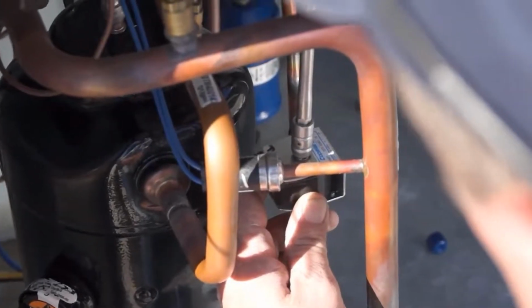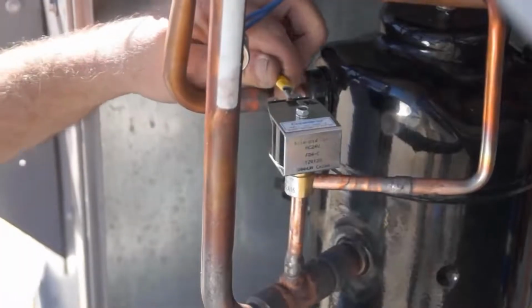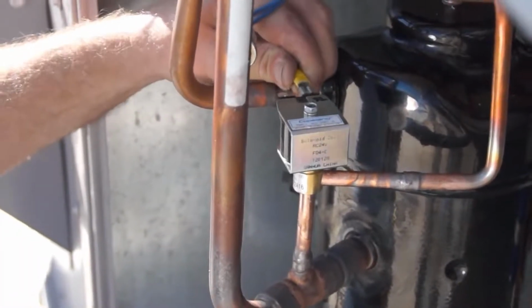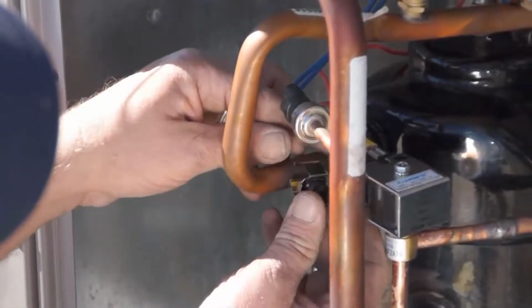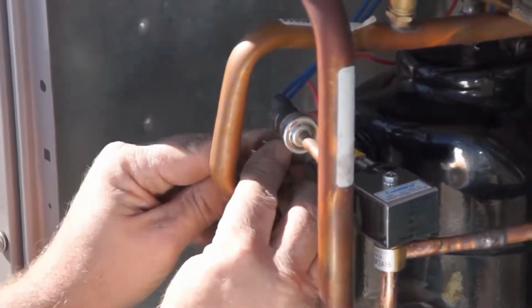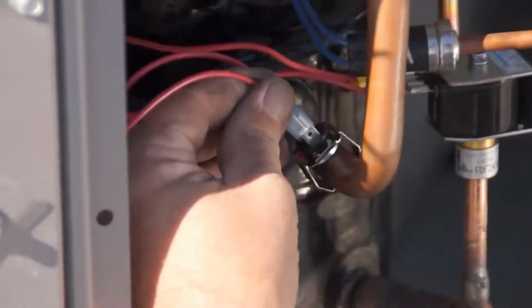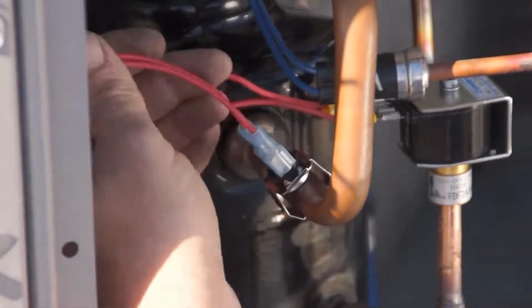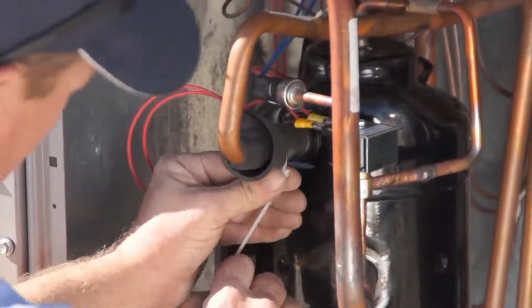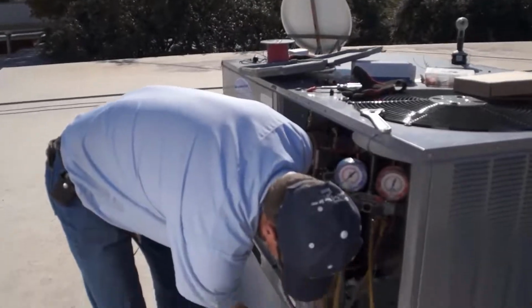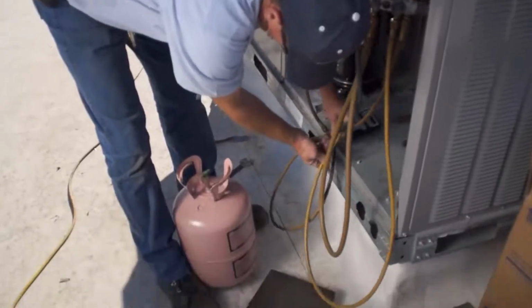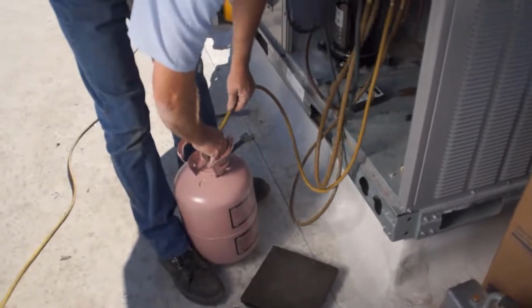Install the 24-volt coil to the newly installed valve. An additional 24-volt wire is required. Install the discharge line temperature sensor, which snaps in place, and properly insulate it. Lastly, add the appropriate amount of refrigerant as specified by the manufacturer.